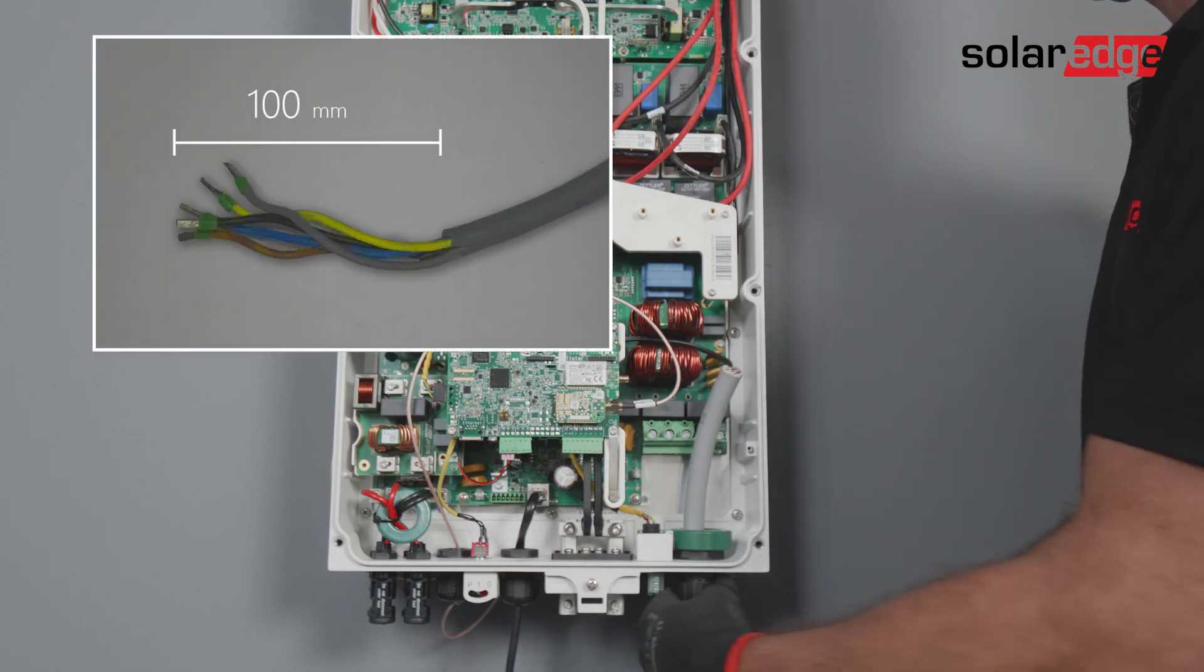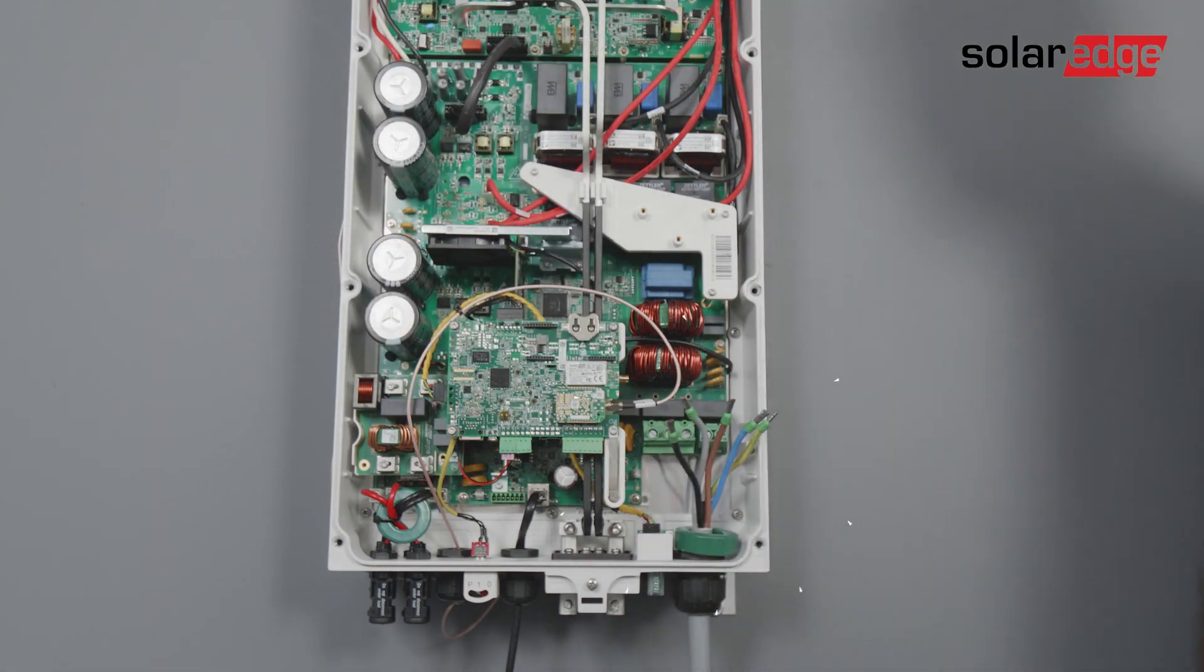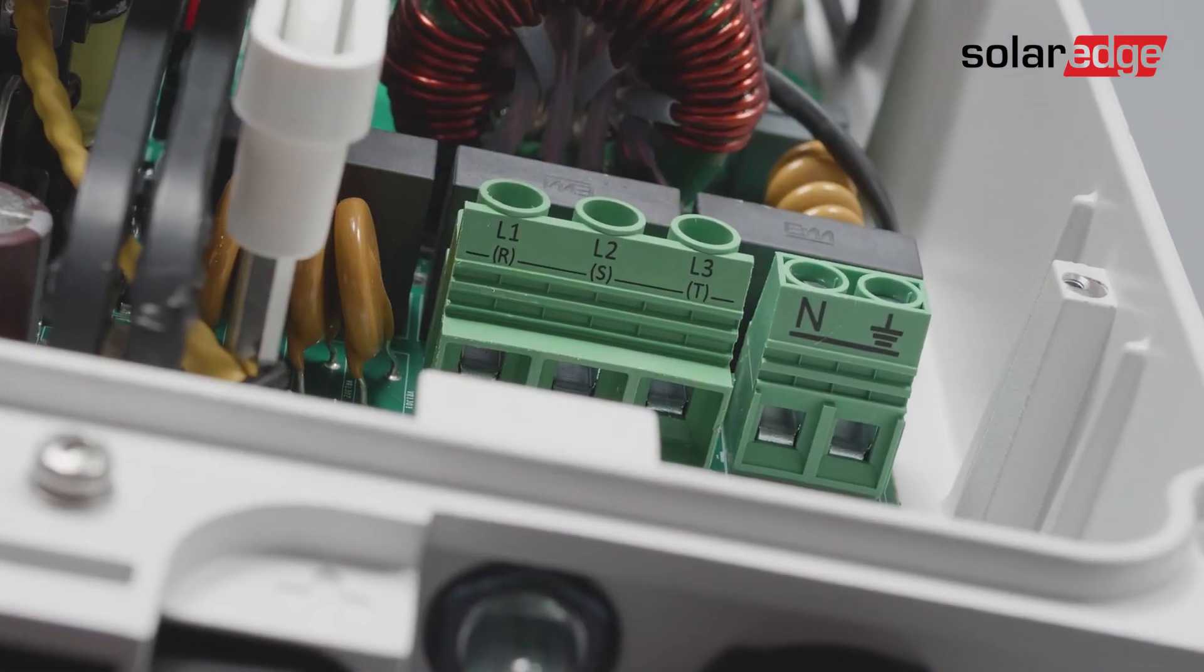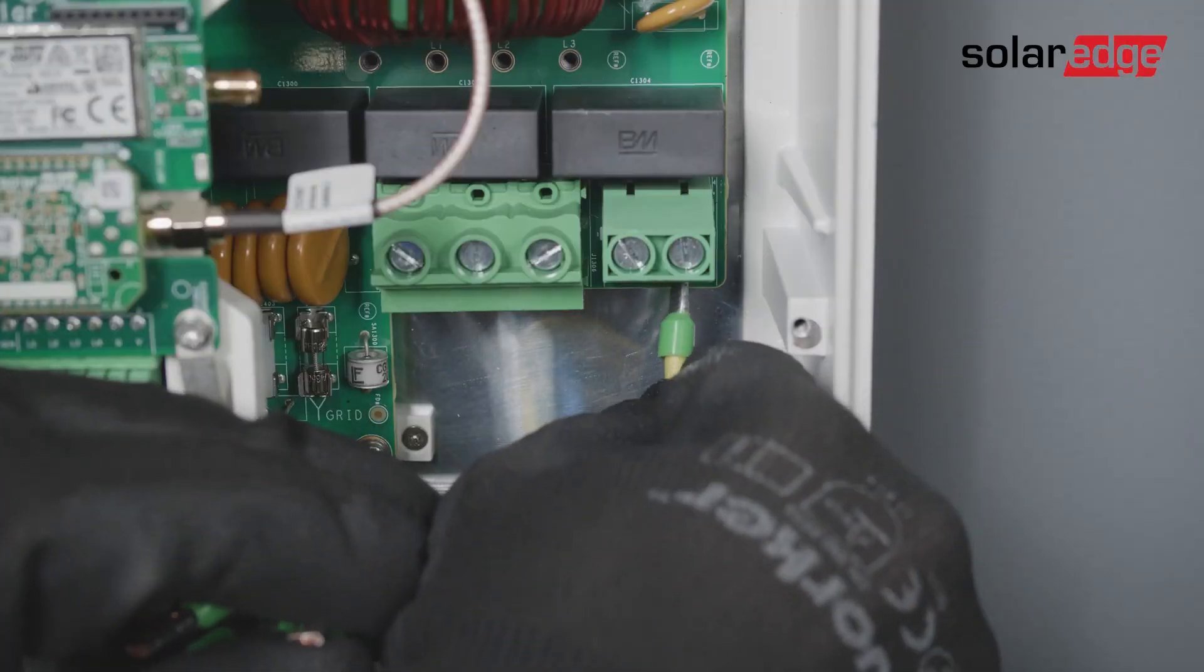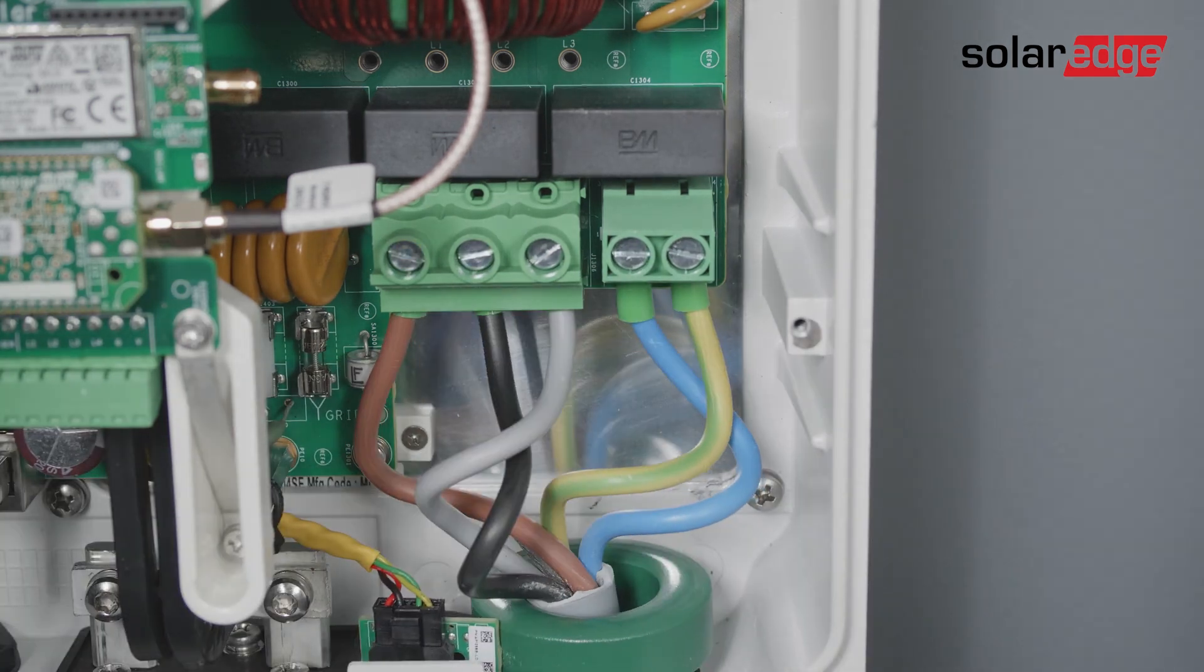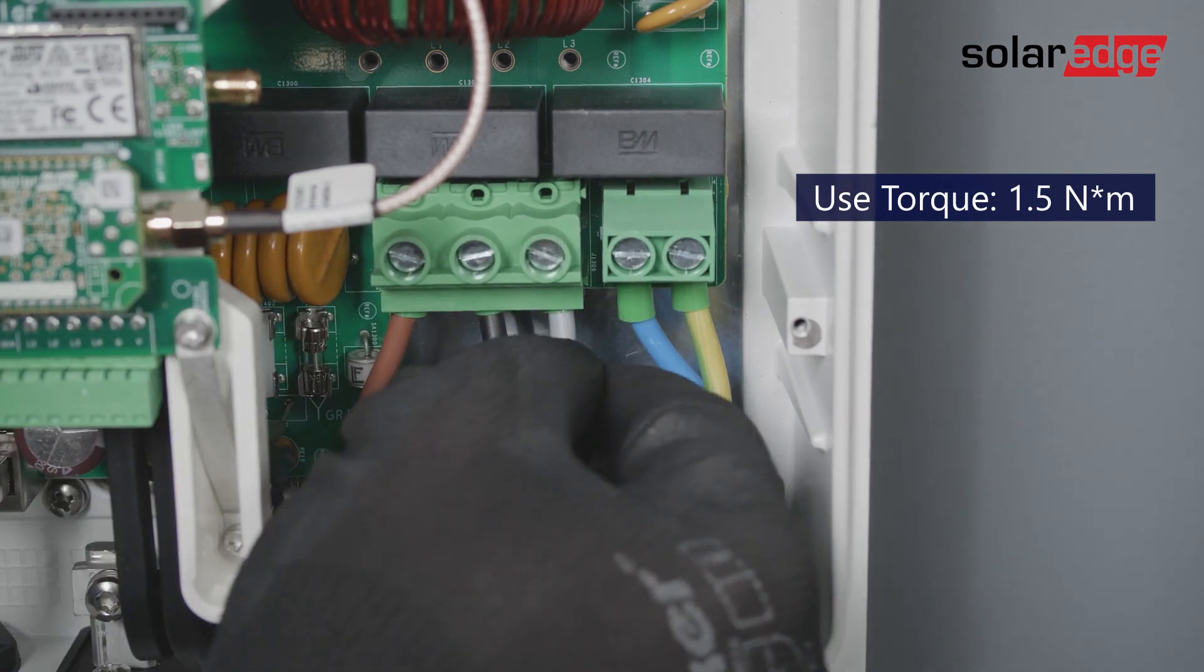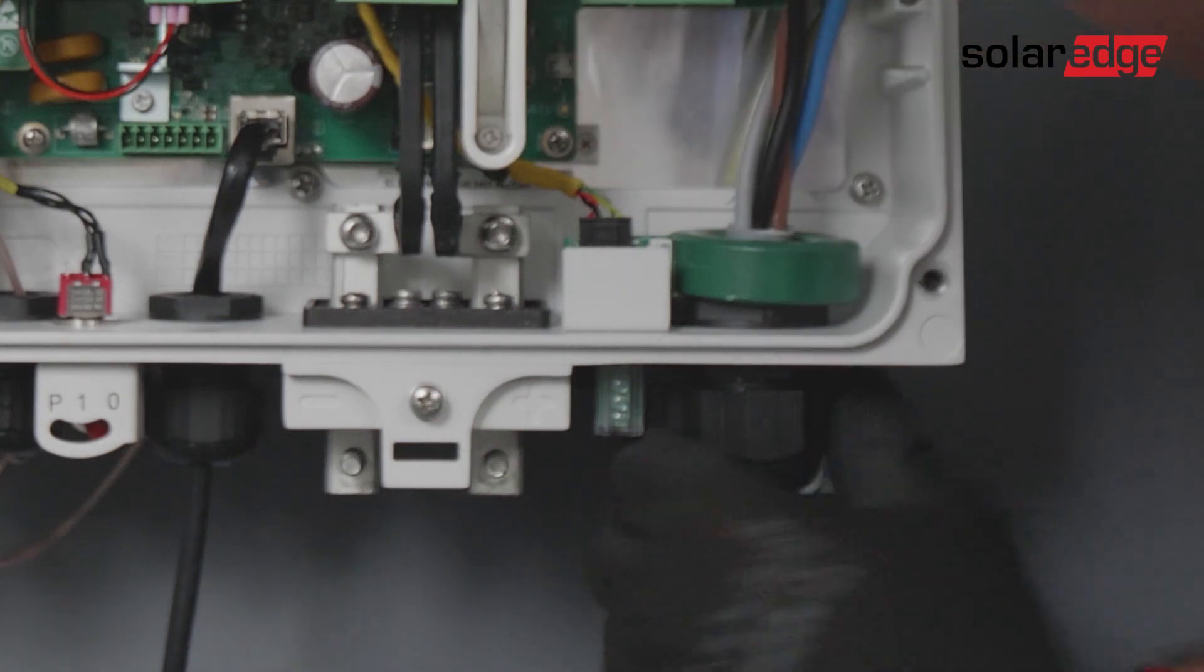Strip 100 millimeters of the external cable insulation and strip 8 millimeters of the internal wire insulation and crimp the wire ferrules. Connect the AC cable to the AC terminals. Please note the marking on the connectors. Connect the grounding wire first. Tighten the terminal block screws. Check that the wires are fully inserted and cannot be pulled out easily. Tighten the AC cable gland.